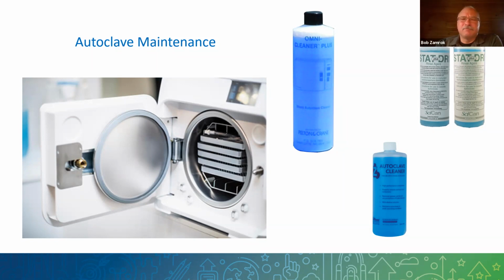This is the one product where no manufacturer is the same - they each offer their own product with specific instructions on how to do it. The Omni cleaner shown here, you'd dilute into 1 gallon or 3 gallons of distilled water, then put it in the reservoir after draining it. You'd run a cycle, then run another cycle with just regular water, wipe everything out, and run another cycle with regular water. Usually it's 2 to 3 cycles total for a cleaning.